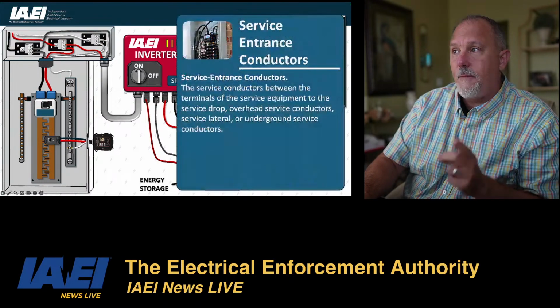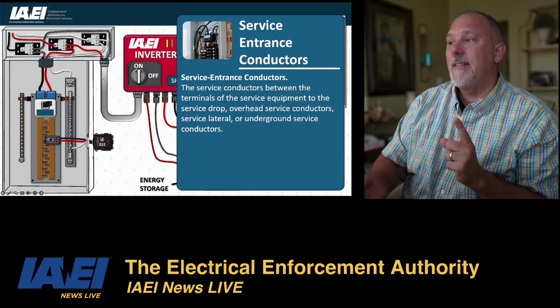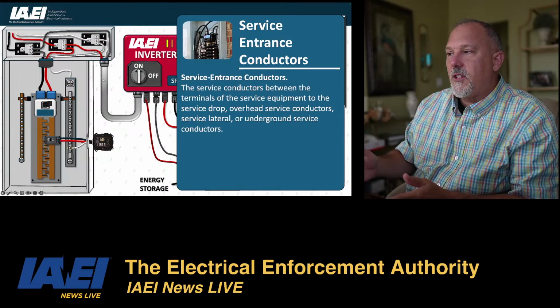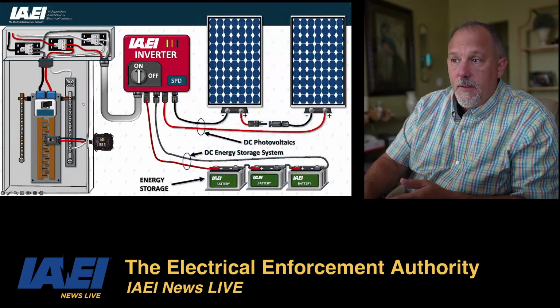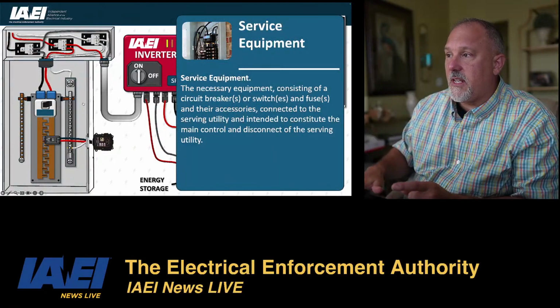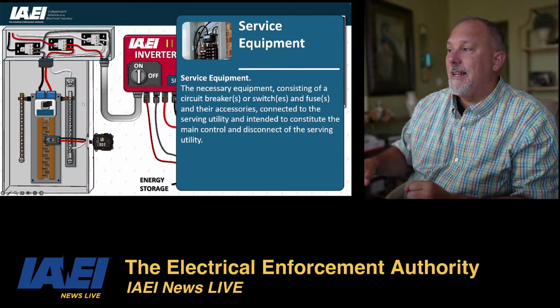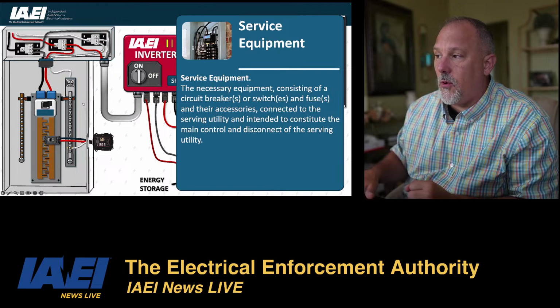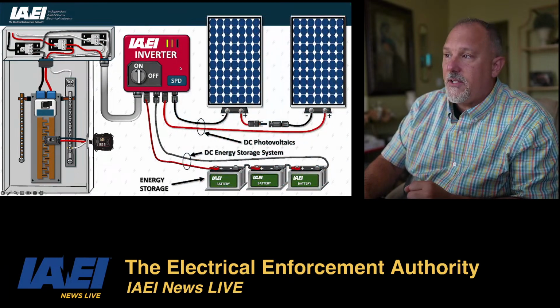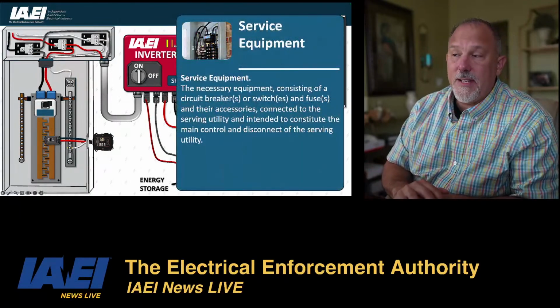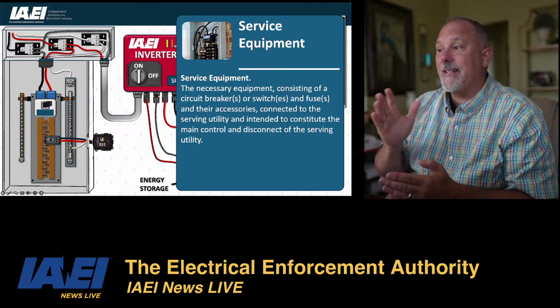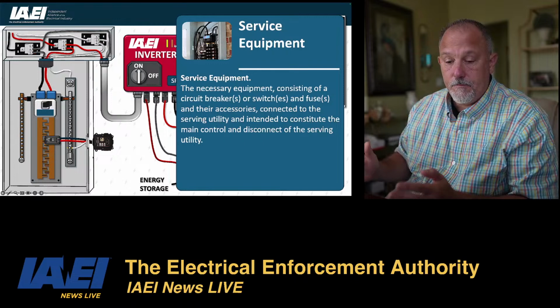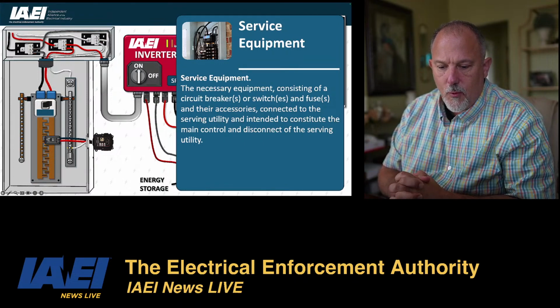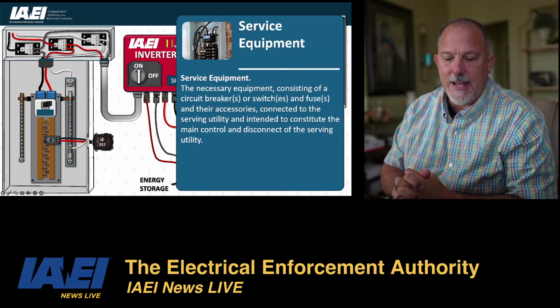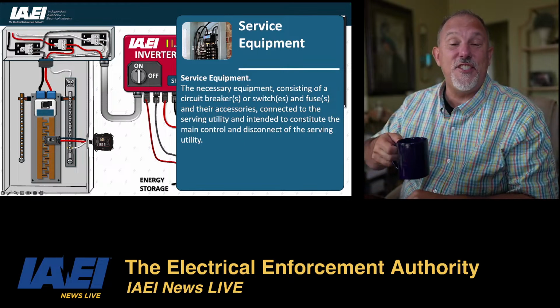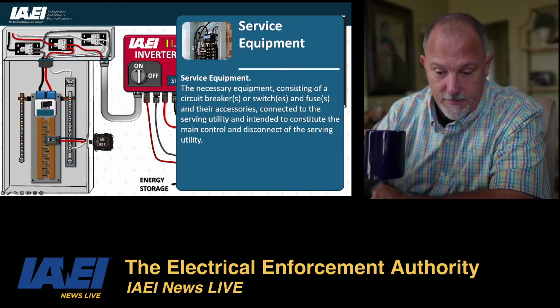Now these conductors are service entrance conductors because, let's look at what it says. The service conductors between the terminals of service equipment. This is service equipment. It's the necessary equipment consisting of a circuit breaker or switches and fuses and their accessories connected to the serving utility and intended to constitute the main control and disconnect of the serving utility. This is service equipment as well. It's connected to service conductors. It disconnects the serving utility from the system. The several definitions of conductor do not mention wire. A conductor is that which conducts or transmits heat, electricity, or sound in the Oxford Dictionary. Thank you, Michael Hofkin.